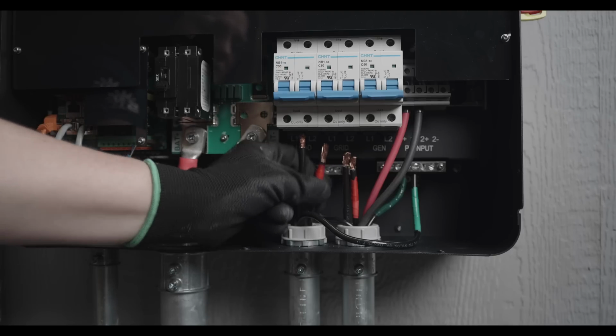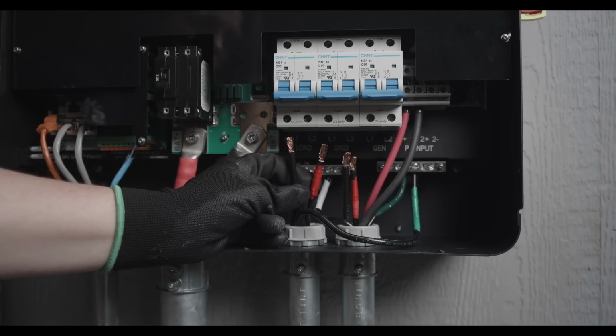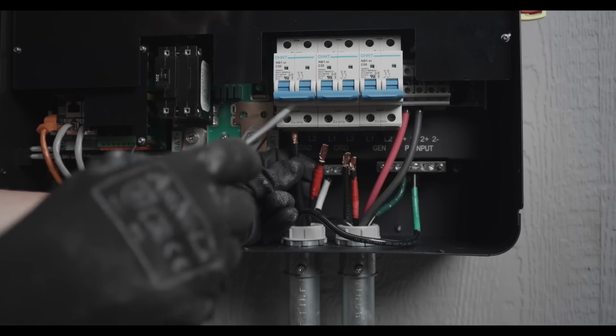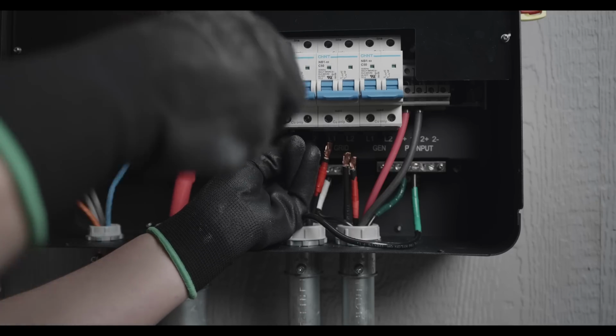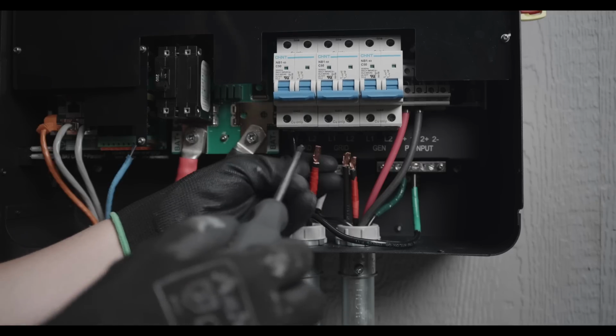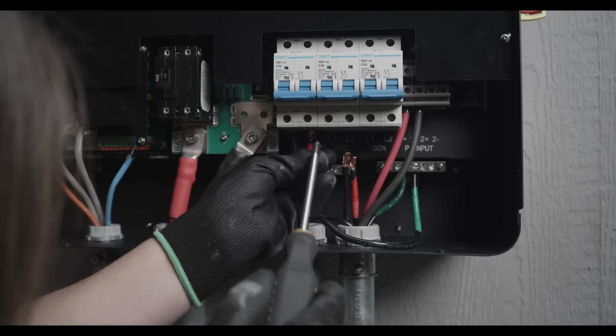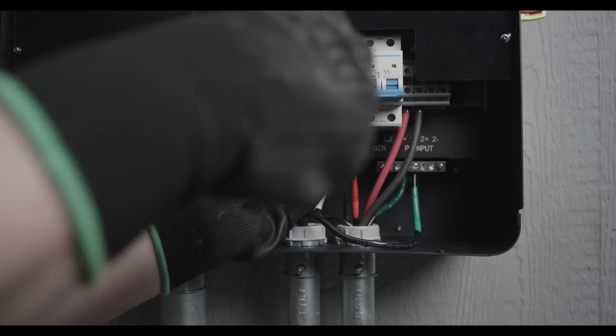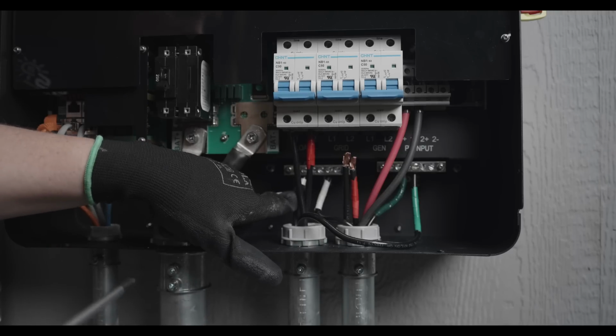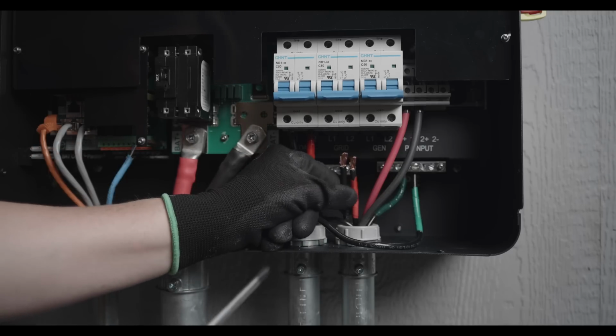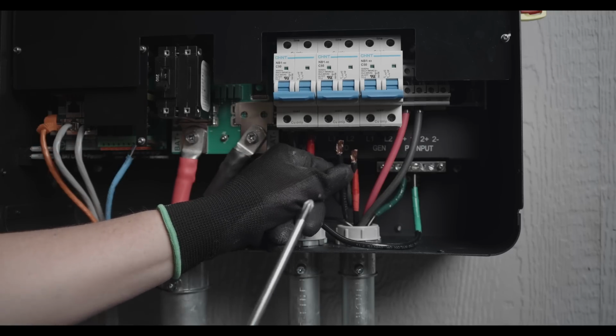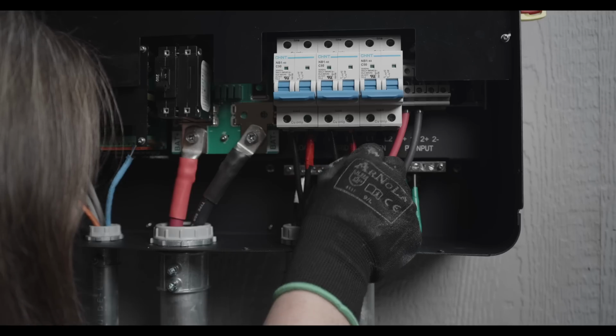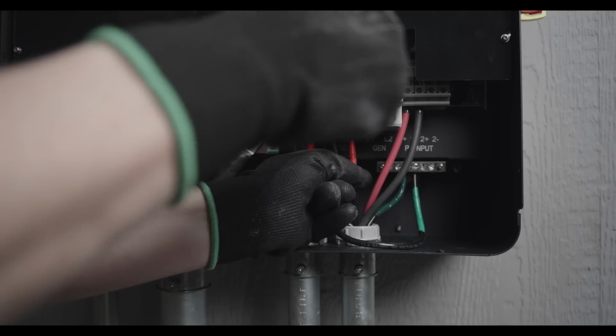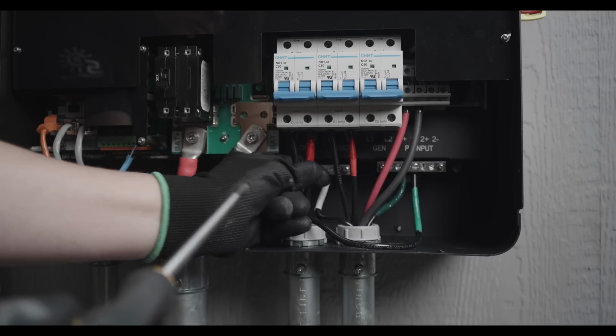When we connect our AC, we have our black going to line 1, so we'll connect our loads, our black to line 1 for our loads. We'll have our red be our line 2. And of course, our white is again connected to our neutral bus bar below. Our grid connections, again, black is line 1. Just give those a gentle tug to make sure they're secure.